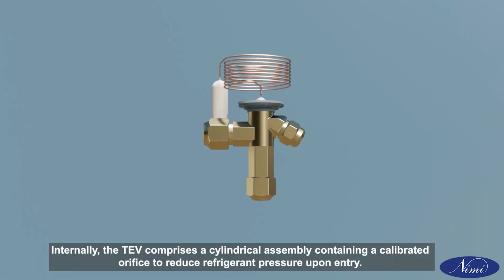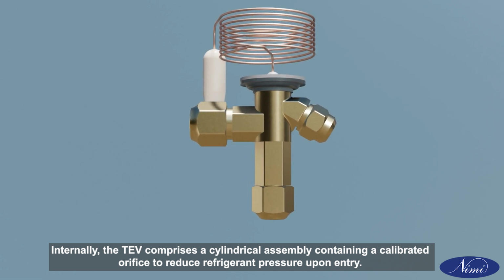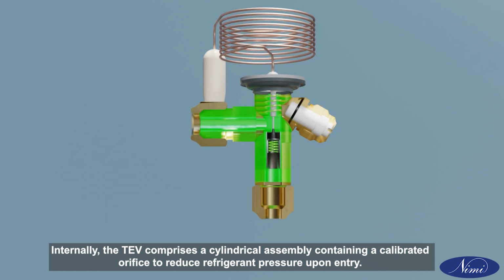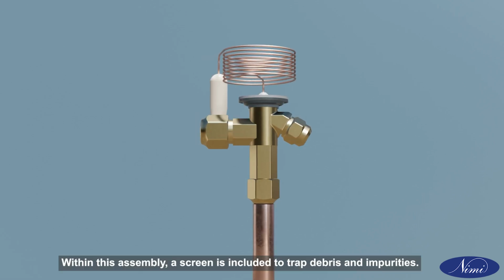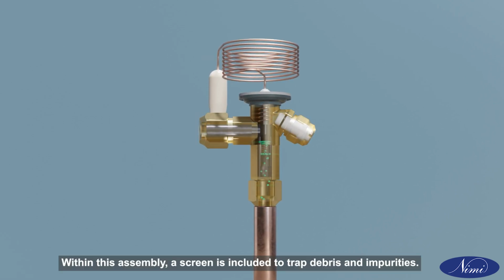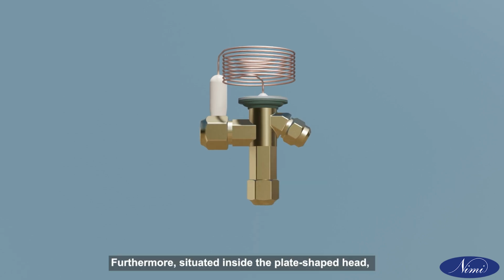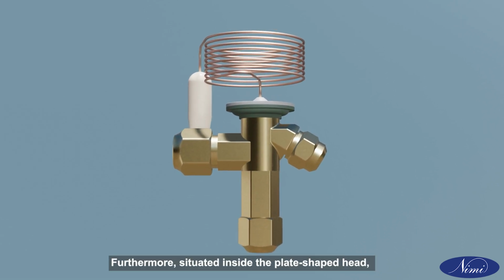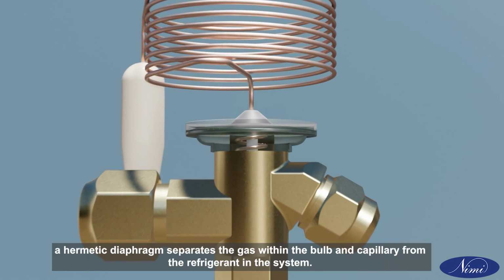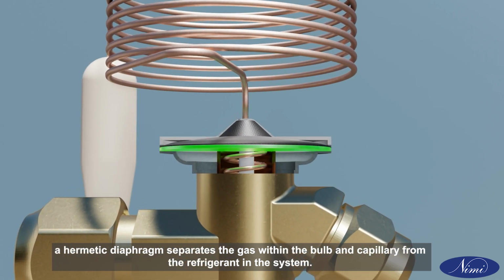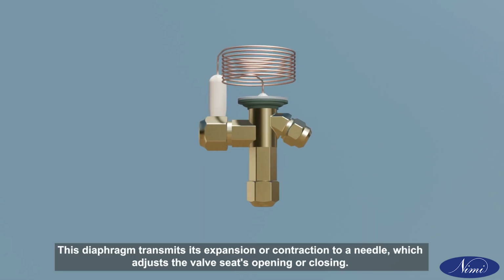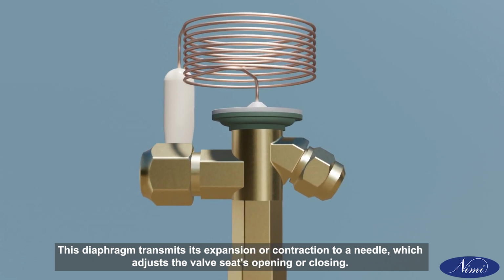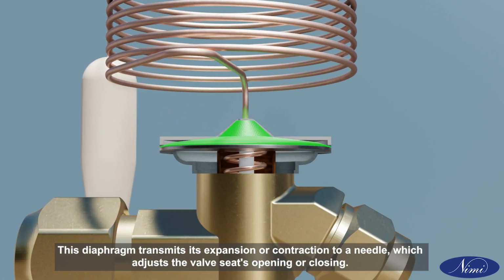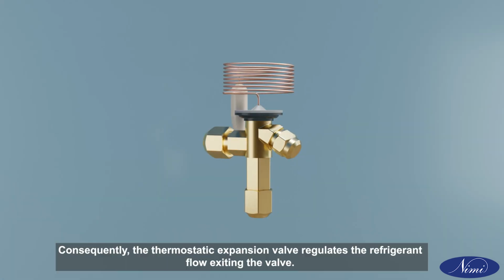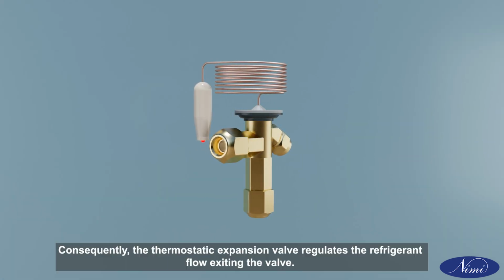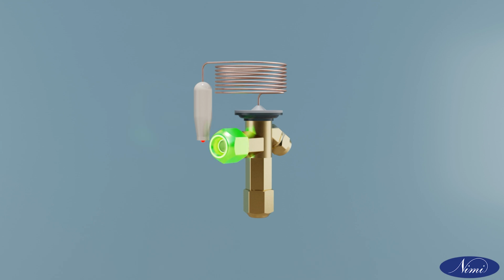Internally, the TEV comprises a cylindrical assembly containing a calibrated orifice to reduce refrigerant pressure upon entry. Within this assembly, a screen is included to trap debris and impurities. Furthermore, situated inside the plate-shaped head, a hermetic diaphragm separates the gas within the bulb and capillary from the refrigerant in the system. This diaphragm transmits its expansion or contraction to a needle, which adjusts the valve seat's opening or closing. Consequently, the thermostatic expansion valve regulates the refrigerant flow exiting the valve.